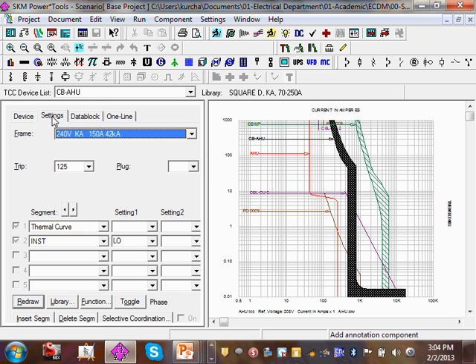So that's the rating of this. Let me just look at the setting. Here's my circuit breaker that I'm dealing with. This happened to be a 240 volt circuit breaker, 150. The interrupting rating of this circuit breaker, can you guys see that? 42 kiloamps. And what was the available in my system? Do you guys remember that? 20, was it 23? So we're good. The available at that panel, we're good. Here's the trip plug. It is 125 amp. Right here is 125 amp. Right here, can you guys see that edge here? That one, how much? 42,000 amps. So right at this point here, this can handle up to 42 kiloamps.